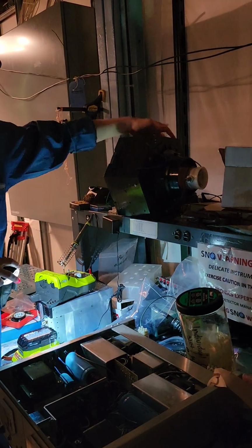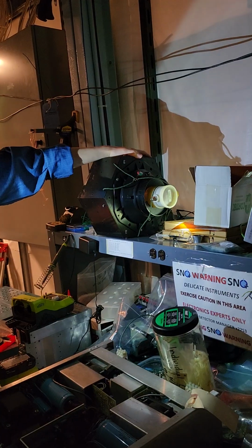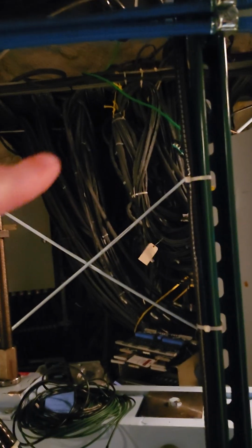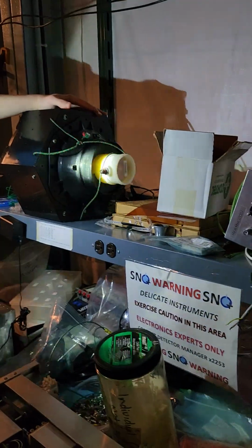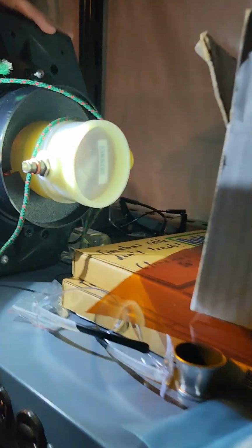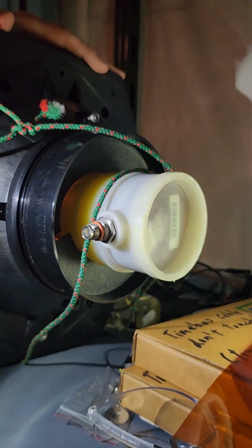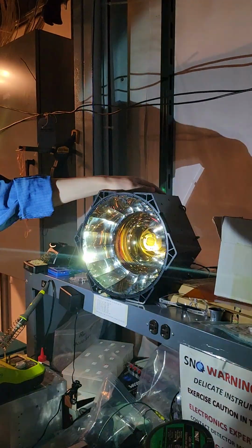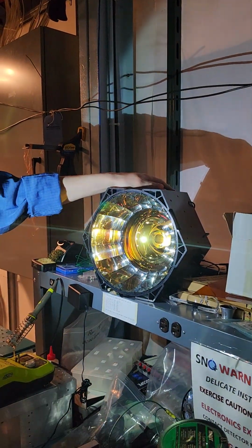Each of these will have a place where a cable connects, just on the back. That's over here. The big cable? These are the big cables. Look behind you, I'll point to these in a second. So all those cables run to the back of the PMTs there. They're O-ring sealed on the outside and the inside to prevent water from coming in, because all of this is working underwater.